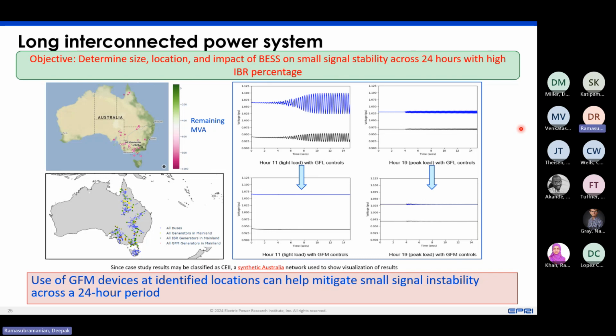Correct. So it is voltage and frequency droop that is embedded at the inverter level, which in the conventional plant is at the plant level, and then we just transfer those directly down to the inverter level. So does that mean it requires some kind of distributed control to maintain the voltage at the plant level? Yes, so that is an extremely important point.